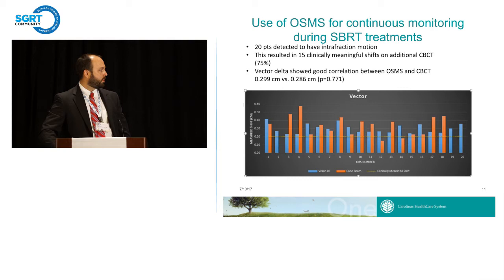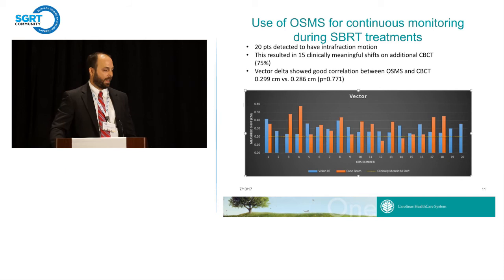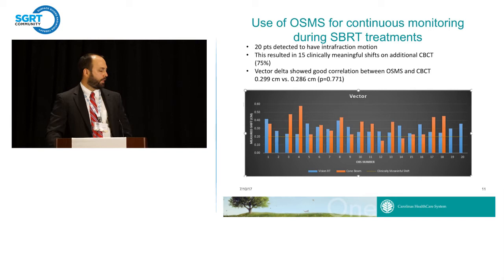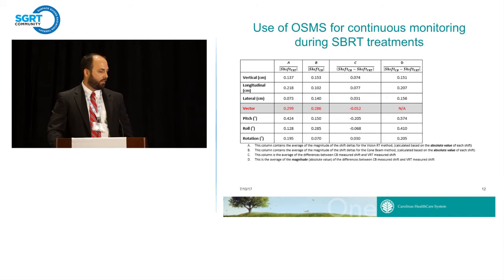There were some instances where OSMS detected a potential intrafraction motion and the cone beam CT shift was actually greater — a couple approaching our five millimeter PTV margin. The important thing is that the system is detecting those cases, catching them at the time of the shift. Looking at individual parameters, the correlation is quite high other than in the longitudinal direction, which was a little different but not statistically so. Overall, the correlation was quite high across all degrees of freedom.